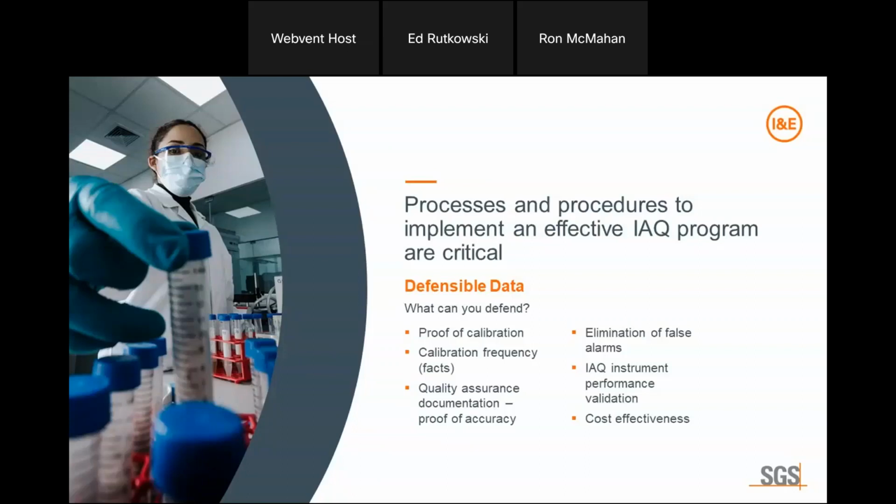And so it's just super critical that, just like everybody on this phone, when you calibrate an indoor air quality meter or a particular instrument, you've got to know it's right. And you do that through showing it test gas. You do it through reference instruments next to you and documenting that. And so I just think it's going to be so critical as these things become commonplace when you start putting these numbers of indoor air quality units into these buildings.